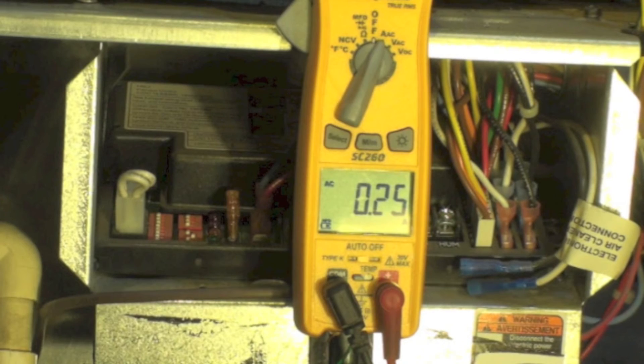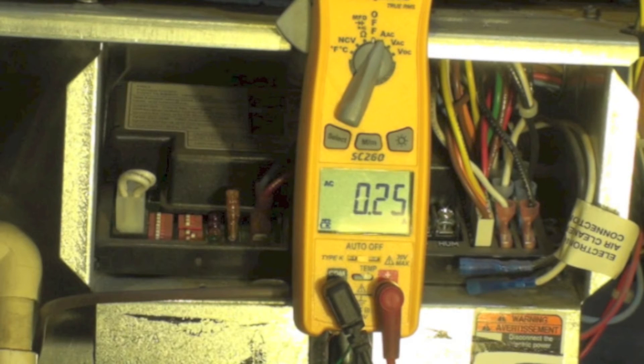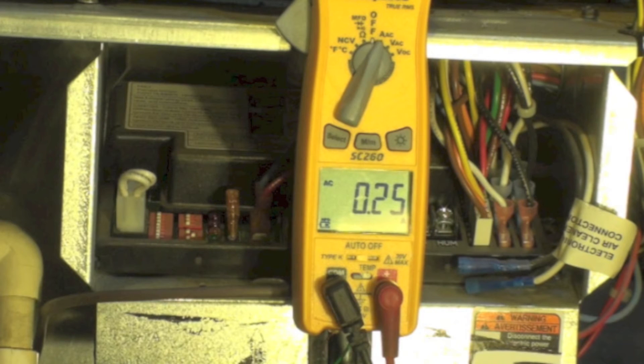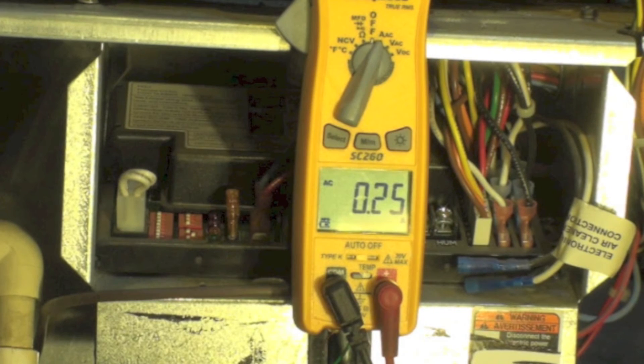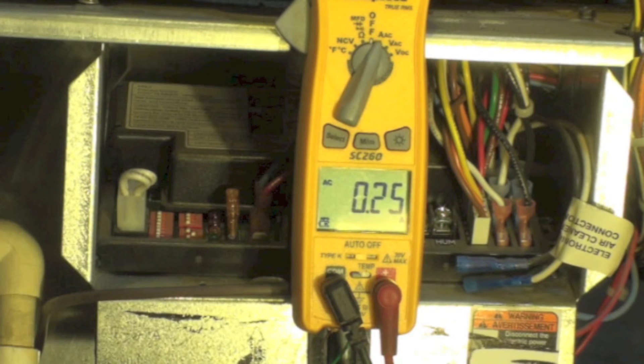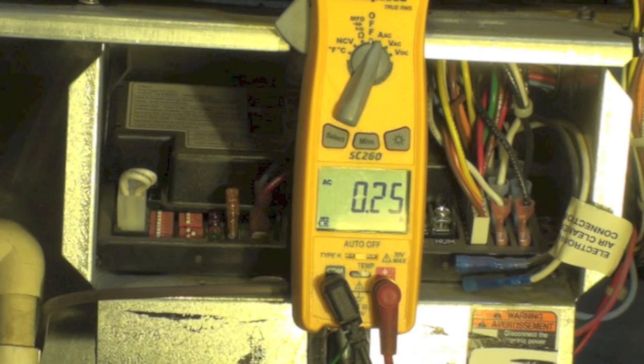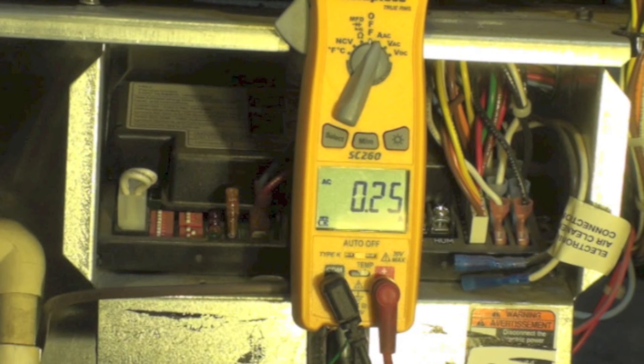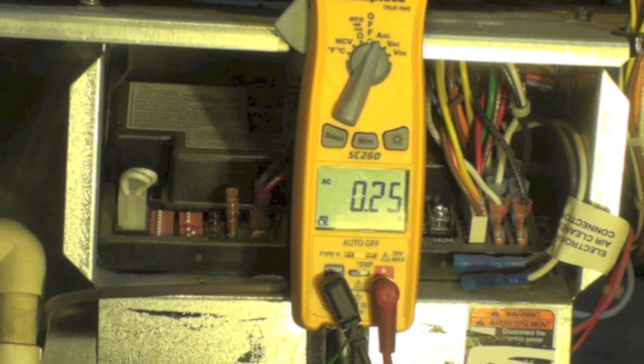As a conclusion: we had about 0.24 to 0.25 amps on the ECM and we had 1.9 on the shaded pole. We're kind of comparing two polar opposites here — the shaded pole is the least efficient of electric motors.